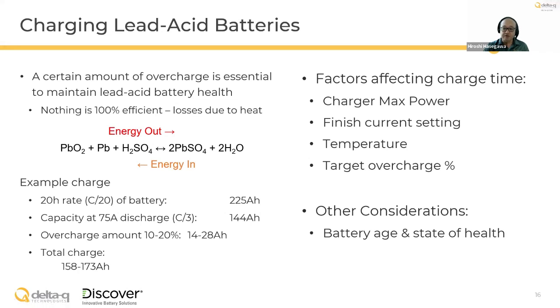Overcharge is different from equalization, a term you hear a lot when talking about batteries. In theory, just the right amount of overcharge on every charge will minimize the need for equalization, which can only be done when the electrolyte is accessible, like in a flooded lead acid battery.